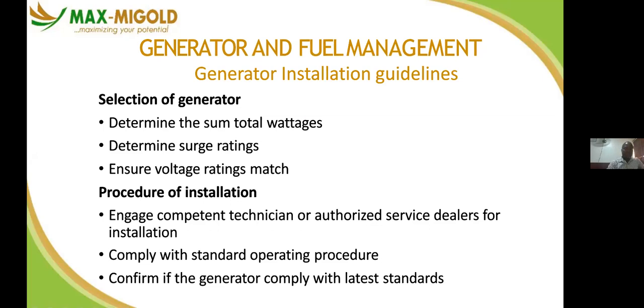So when you are selecting your generator, you consider the following, just like when you are designing your power installation. Determine the power rating of what you want from your load analysis. You must do your load analysis to be able to determine the power demand for the load you have calculated. So you have to get it right. If your total power is 30 kVA that you've calculated, you are not expected to go and buy exactly 30 kVA. Why? Because there must be some diversity factor. You must create an allowance in terms of transient current or a sudden rise in power or surge.